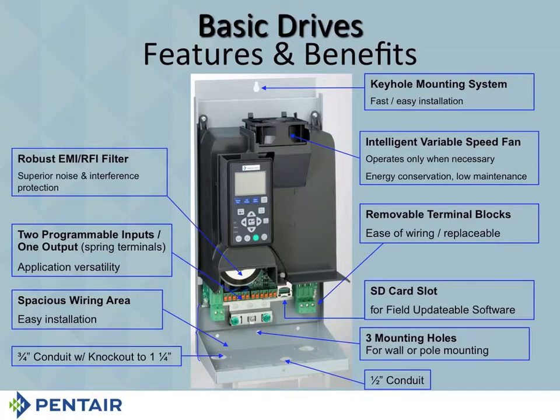A robust EMI RFI filter. EMI means electromagnetic interference. RFI means radio frequency interference. Electromagnetic interference means you can set this drive, turn it on, and when you turn it on, it's not going to make the garage door go up or anything silly like that. Also, you can take an AM radio, put it within about a foot of the drive, and it should work just fine. By the way, if you are getting some crackling on your AM radio, it probably means you're not grounded properly, but the drive will tell you that too.